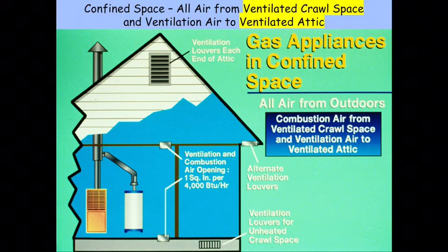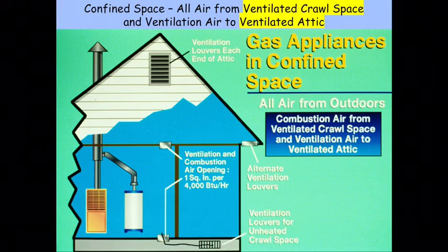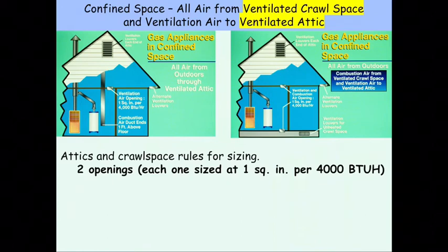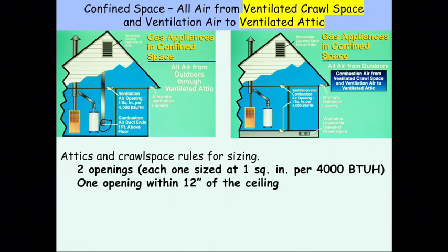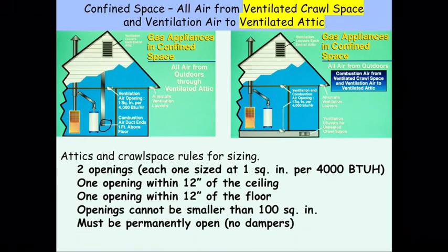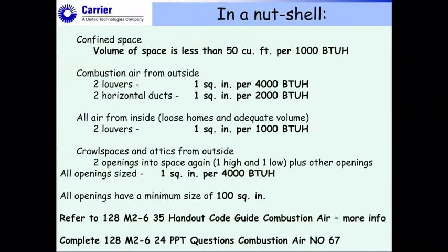In the crawl space application, ventilation air is drawn from a louvered unheated crawl space up into the mechanical room. The rules are essentially the same: each opening sized at one square inch per 4,000 BTUs, one opening high, one opening low — within a foot of the floor in this case — not less than 100 square inches, and no dampers.